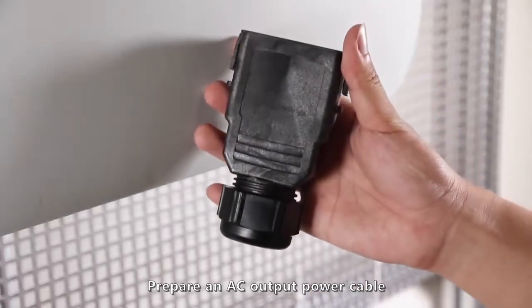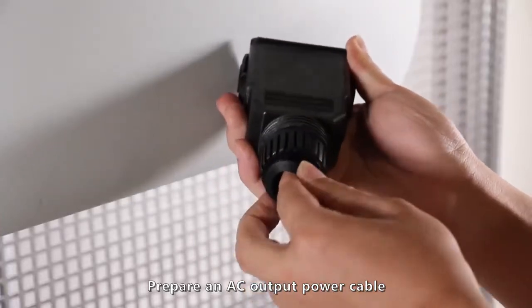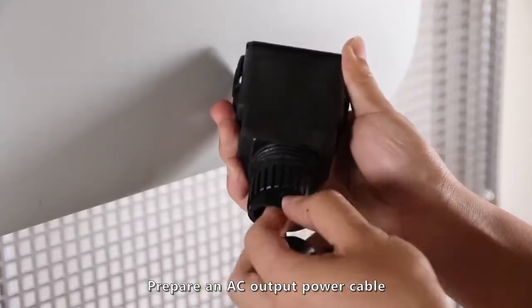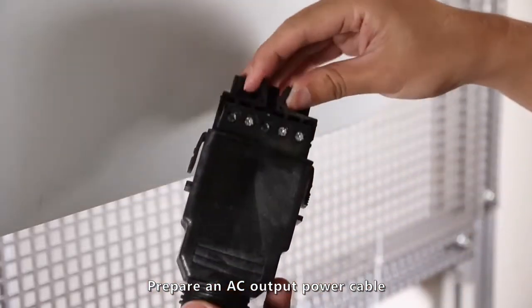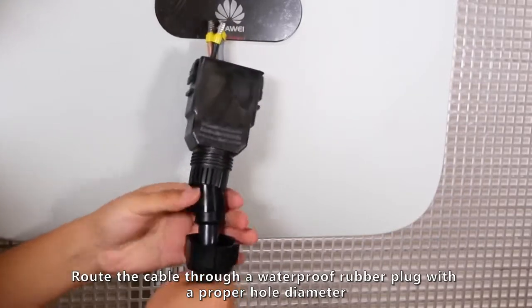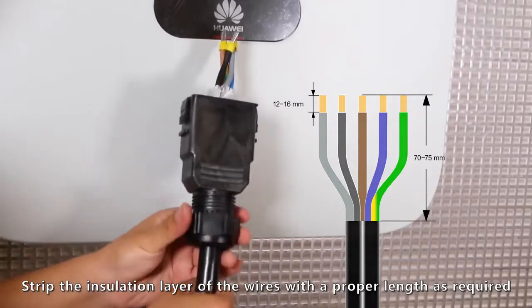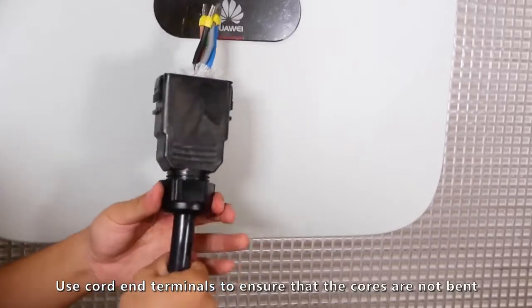Prepare an AC output power cable. Route the cable through a waterproof rubber plug with a proper hole diameter. Strip the insulation layer of the wires to a proper length as required. Use cord end terminals to ensure that the cores are not bent.